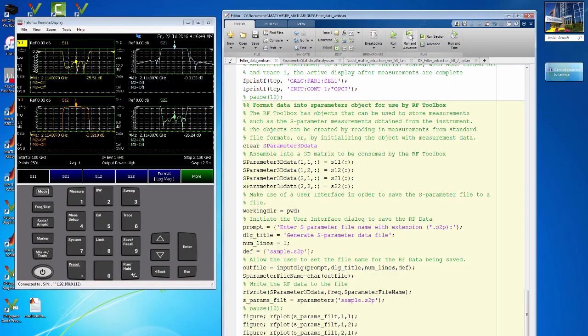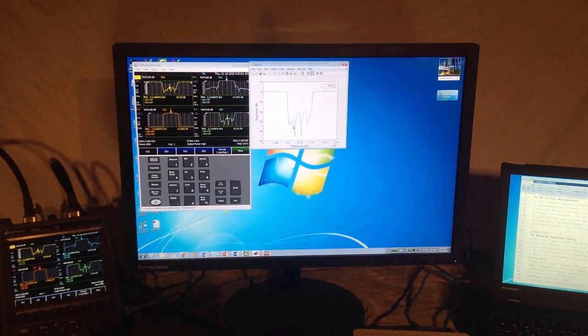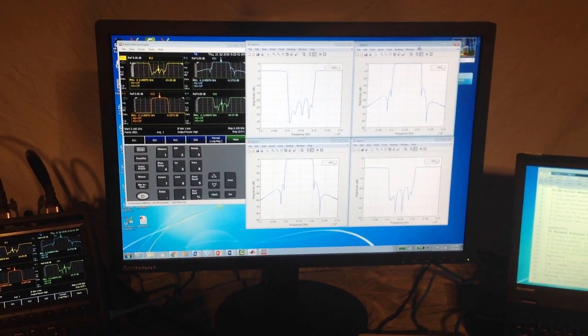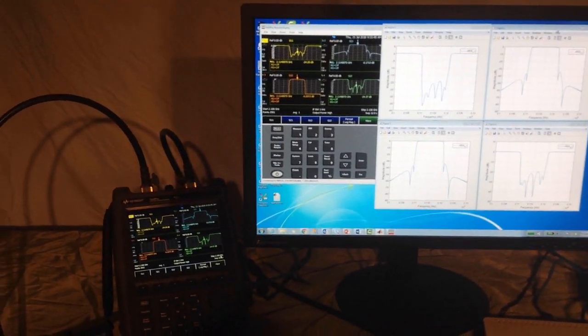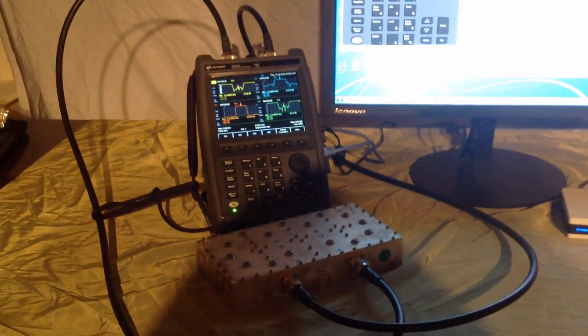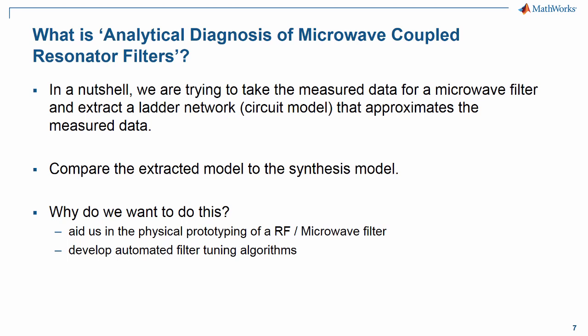Now that all of the trace data is in MATLAB, we are going to put it into an S2P file. The dialog box will allow us to name the data file. Plots of each of the S-parameter elements are then made using functions from RF Toolbox. The network analyzer has been returned to its original state and we have successfully imported S-parameter data from the VNA back into MATLAB. Now that we have completed the process for accessing network parameter data from a VNA, let's turn our attention to the diagnosis or model extraction of the microwave cavity filter.